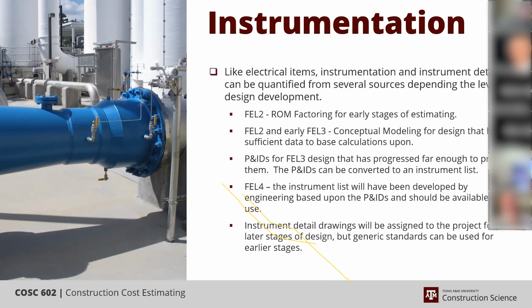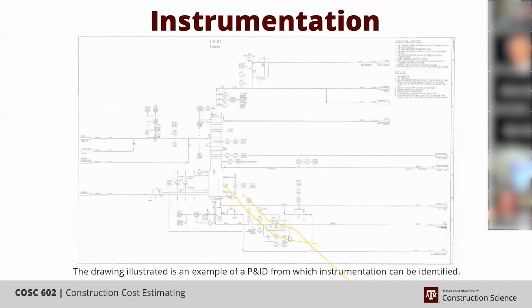But if you were to take them all side by side, they may not be identical, but you'll notice they're all actually quite similar because they're all modeling a standard approach to installing a start stop button on a stand, or supporting a transmitter off the side of a pipe, next to an orifice plate that's reading the differential pressure between each side of the orifice plate. So there's only so many ways you can do that, and they're all quite similar, even though they may be different or owned by different entities.